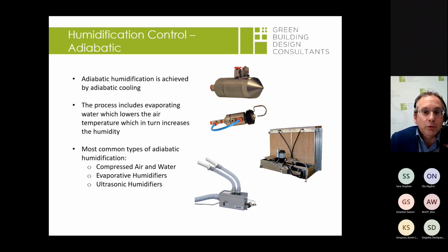So you end up doing this seesaw effect, trying to put 55% humidity in once it leaves the humidifier, knowing that the next time you heat it up another 3 or 4 degrees, it's going to drop back to 50%. So it becomes quite technical to achieve, but it is possible. You can see there I heated the air up to 35 from outside, then cooled it down to 18 to get the water back into it, and then had to heat it up again to lose a bit more humidity to get to where we want. But it can be done.